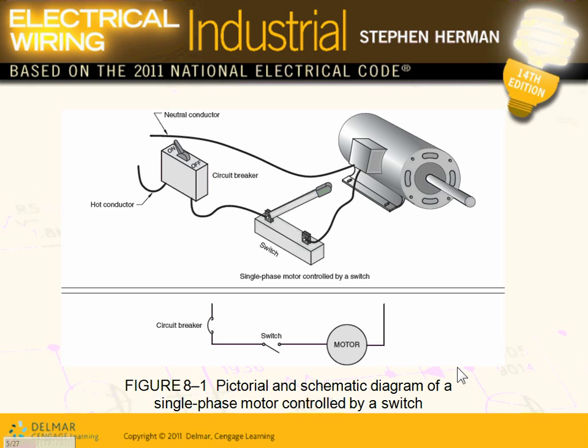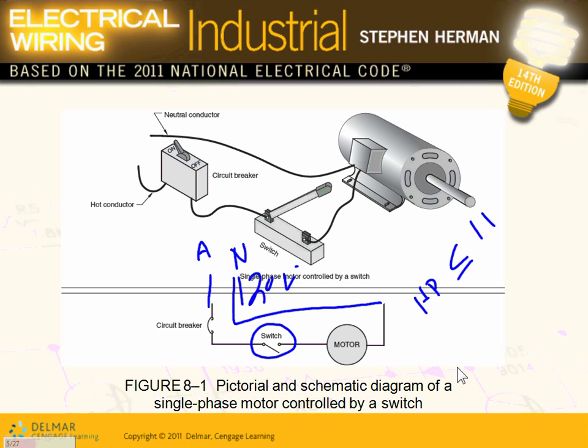Here's the cheapest way. This is how you wire a motor fan — a fan in the bathroom. That's basically how you wire a bathroom fan: you grab phase A and neutral, you power it from 120 volts. How do you control it? With a snap switch. Snap switches are good up to a fraction of horsepower — if equipment is equal to or less than one horsepower, you can control it with a snap switch on the wall.